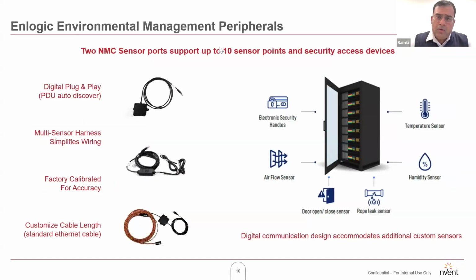This means all your alarms, sensors, door handles, etc. continue to function and you can pull information from the PDU. I briefly mentioned the two sensor ports earlier. The Enlogic PDUs allow you to connect up to 10 sensor points per PDU, so typical environmental monitoring items like door handles, temperature and humidity sensors can be connected directly to the Enlogic PDU. This is per industry standard and something you'll find across most PDU manufacturers.